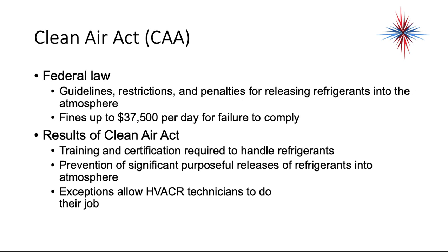The Clean Air Act, CAA, is a federal law. It provides guidelines, restrictions, and penalties for releasing refrigerants into the atmosphere. You can have fines up to $37,500 per day for failure to comply. The results of the Clean Air Act were training and certification required to handle refrigerants, prevention of significant and purposeful releases of refrigerants into the atmosphere, and exceptions to allow HVAC technicians to do their jobs.